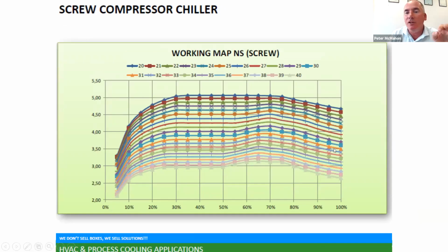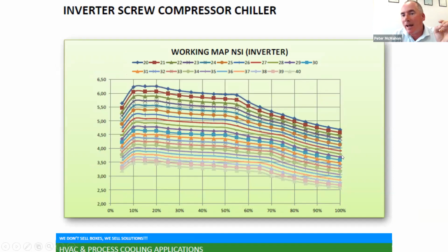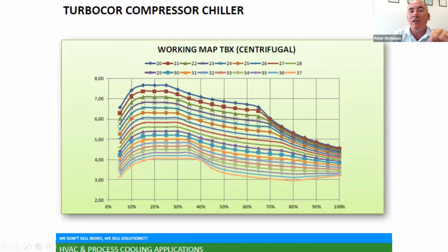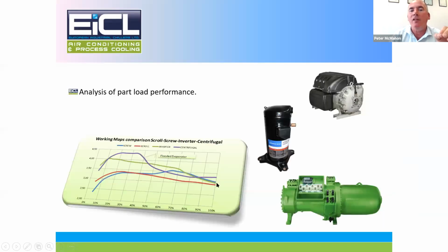If we look by comparison, the non-inverter screw, again, you can see at 100% load, it's typically at its least efficient. If we look at the inverter screw, again, it's at its least efficient at 100% load. Obviously, you'll see the part load efficiency gets much better for the inverter screw compressor. And the final one here, I have the Turbocor. You can see it's very, very efficient in part load efficiency. So the common theme here, quite simply, is most chillers are at their least efficient at 100% load. So where we often have two or more chillers on a system, why do we run them to 100% load? Well, we really shouldn't. Again, it's just because that's what we've been taught to do for so long.